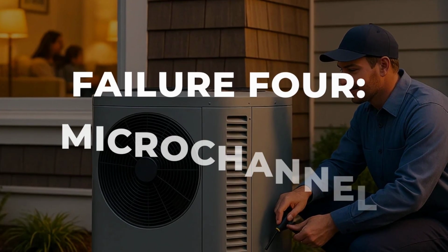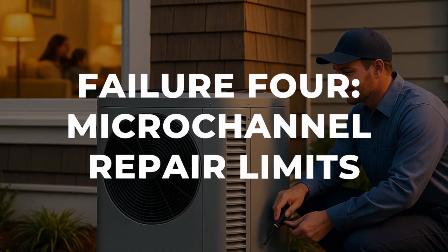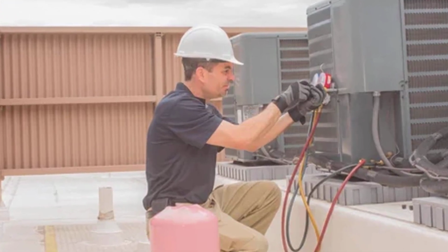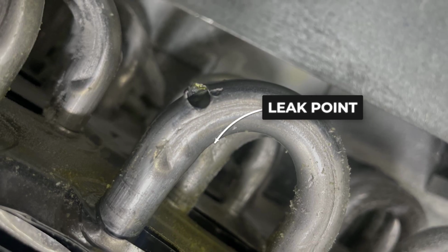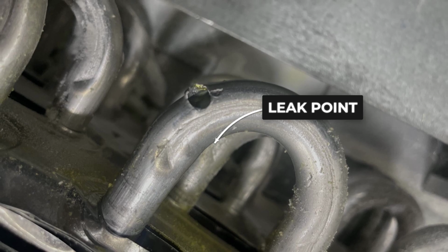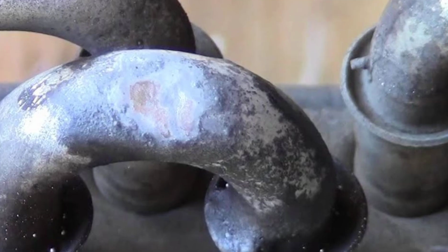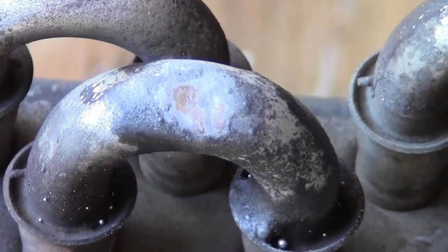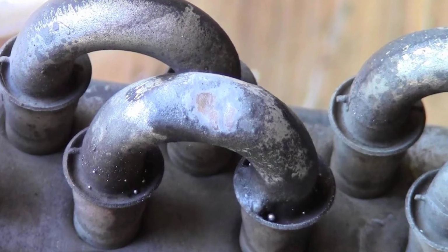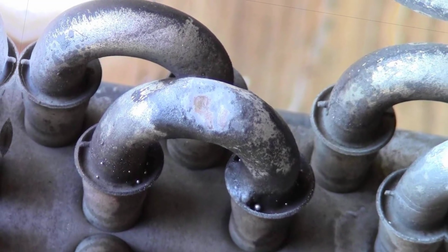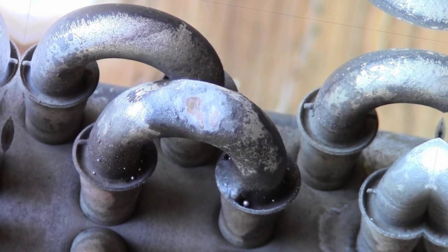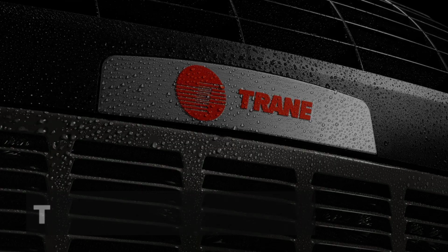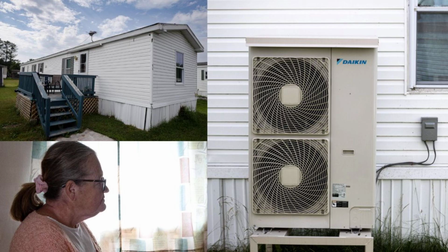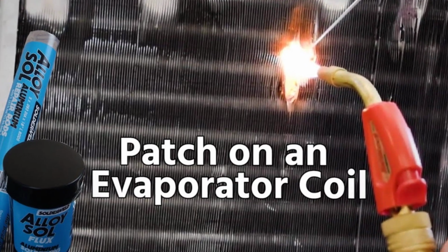Failure 4, the microchannel field repair reality. Suppose your outdoor unit uses a microchannel coil and it springs a leak in the flat tube area. Trane's service bulletin describes a temporary repair: epoxy application, aluminum wrapper, controlled heat cure at specific temperature limits, especially at copper to aluminum joint transitions. Temporary. The manufacturer's own bulletin uses that word. This is not a 20-year fix. This is a hold it together until replacement fix.